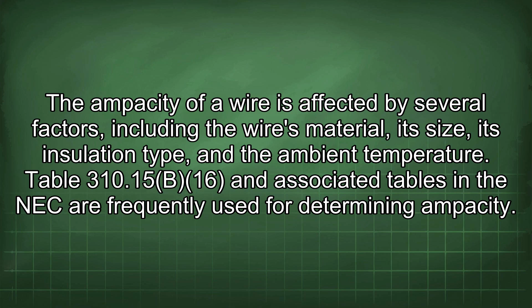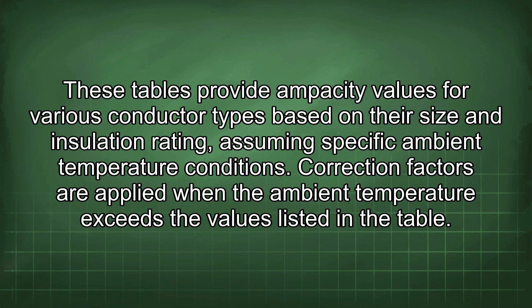Table 310.15(B)(16) and associated tables in the NEC are frequently used for determining ampacity. These tables provide ampacity values for various conductor types based on their size and insulation rating, assuming specific ambient temperature conditions. Correction factors are applied when the ambient temperature exceeds the values listed in the table. Adjustment factors are applied when multiple current-carrying conductors are bundled together in a raceway or cable, as heat buildup can reduce the ampacity of each conductor.